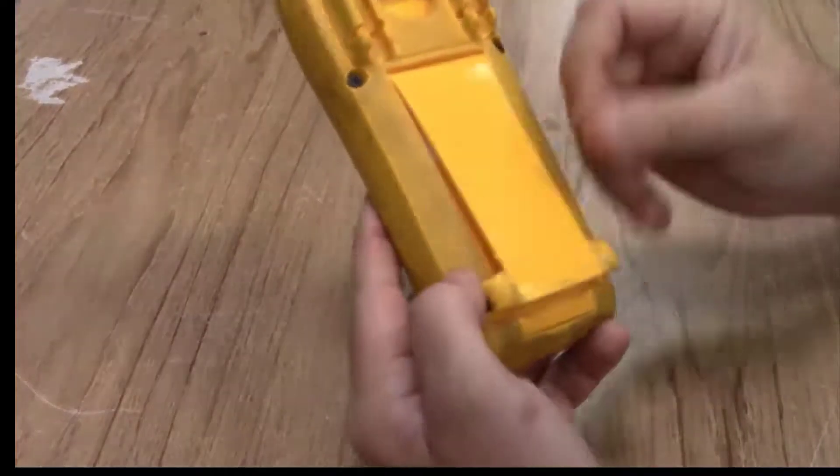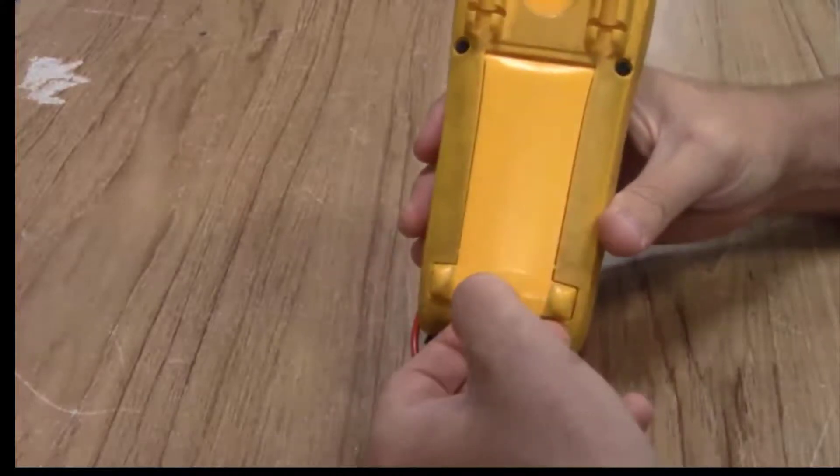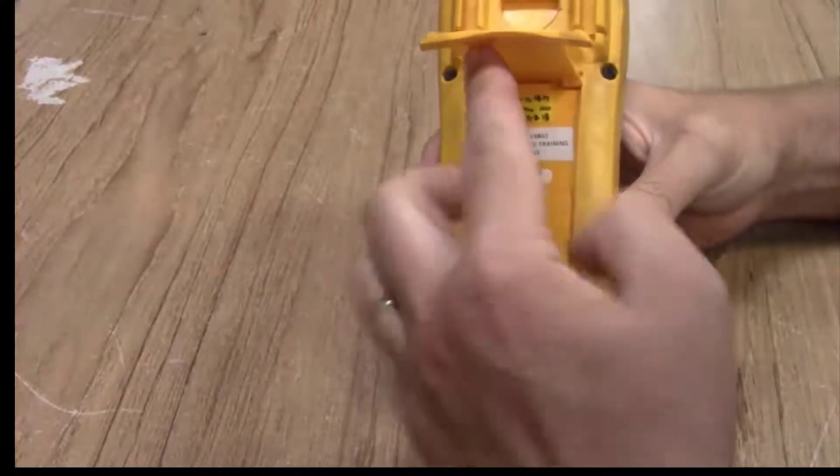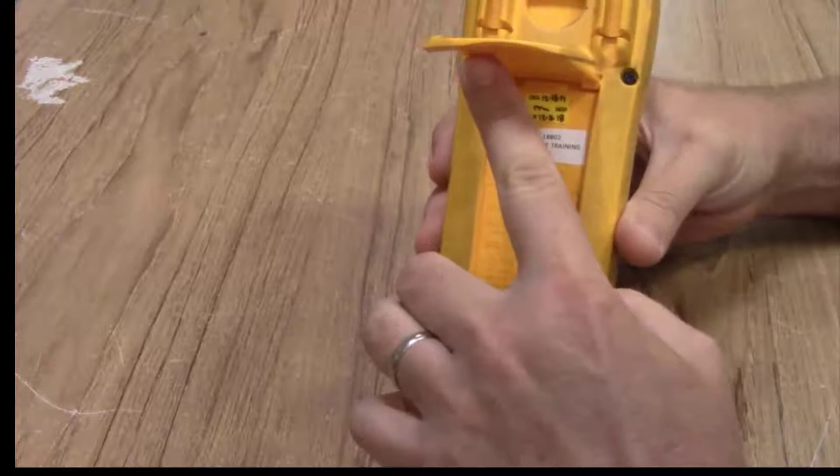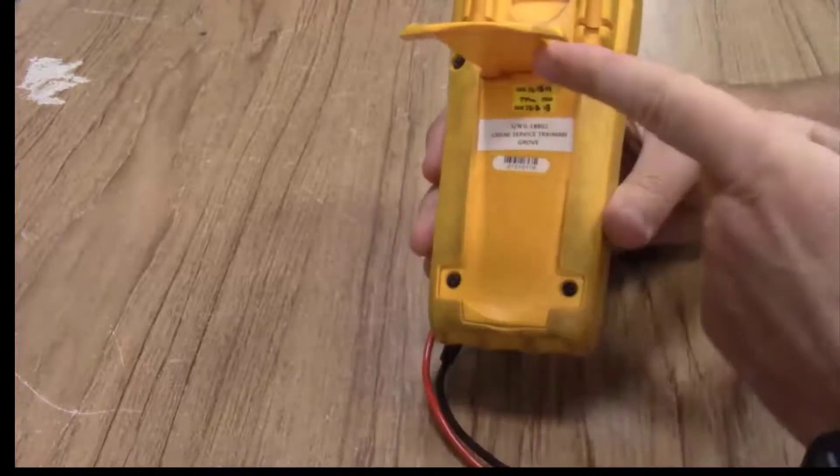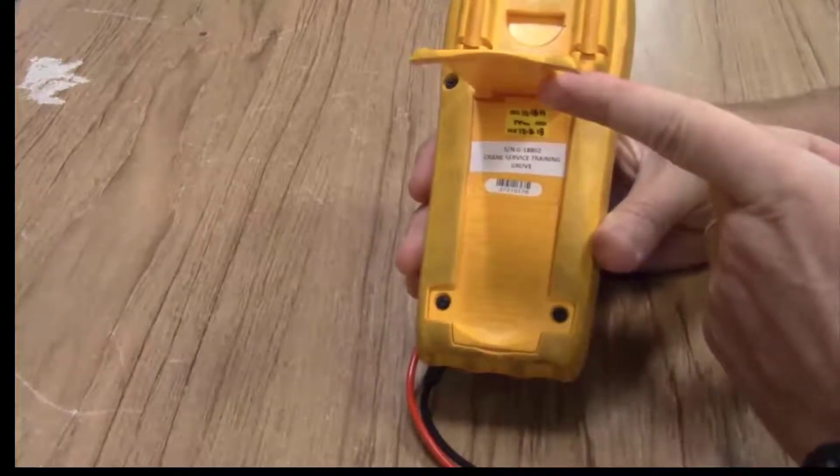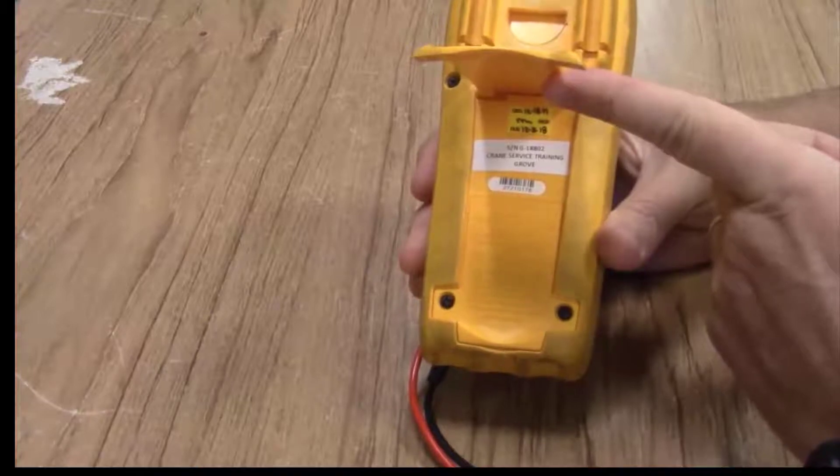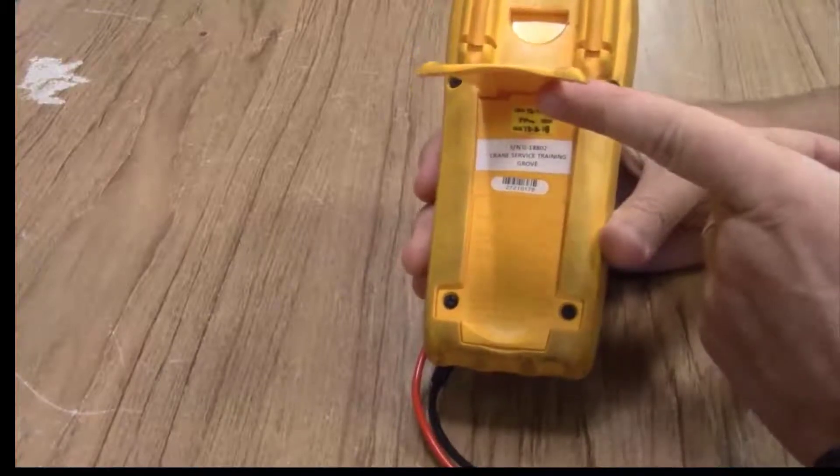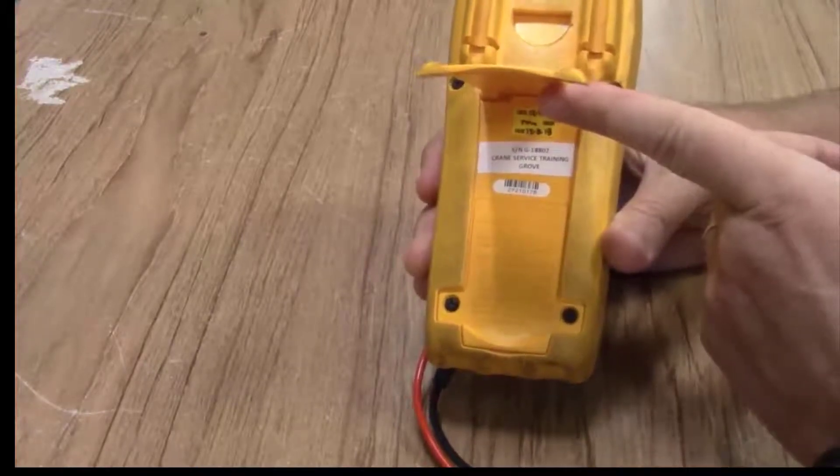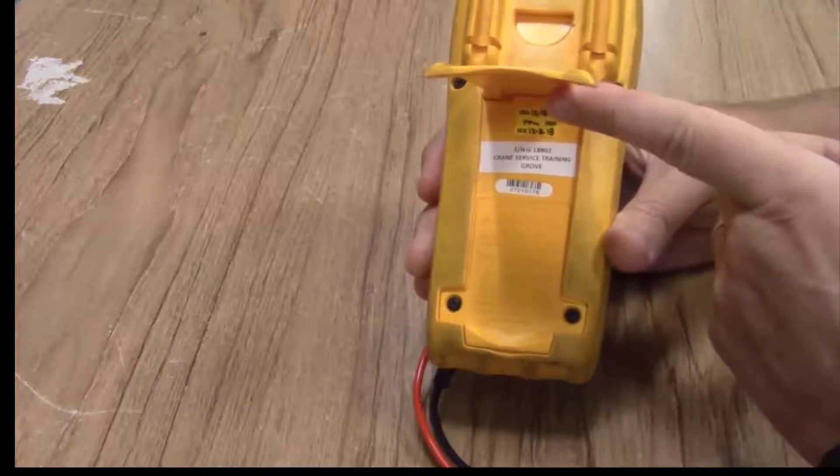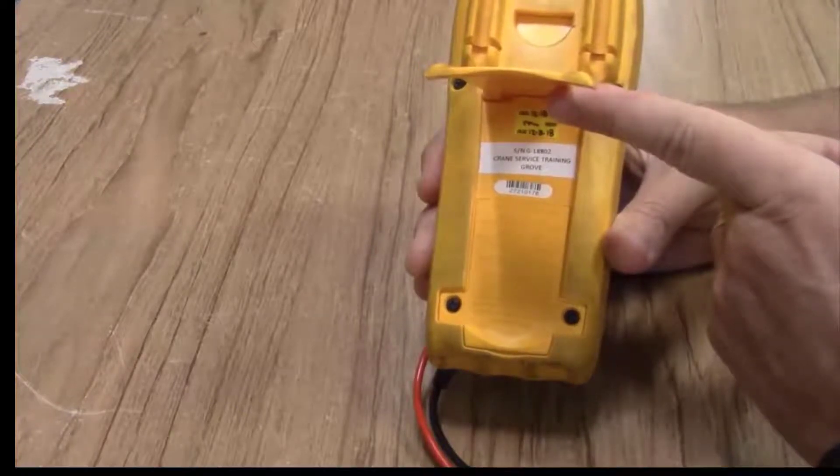So you can also flip the meter around on the rear. On this model, you have a prop and under the prop there is a spot to take out two screws so that you can replace the nine volt battery that's in them. There's also a couple of fuses that could blow for protection purposes that are also replaced in the same compartment on the back of the meter.